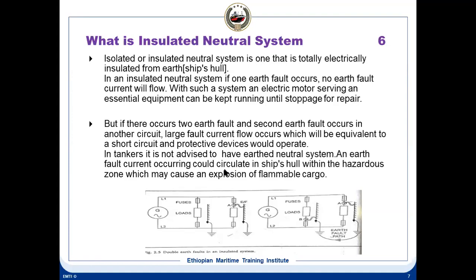So hope you understood what insulated neutral means. The purpose of the insulated neutral system is that in case of a single earth fault in one of the phases, your critical machinery should keep running, for example a steering gear motor. Suppose there is an earth leakage on one phase, it should still run. But if there is an earth leakage on two phases, it can cause a short circuit and the protective devices will trip the system. So it is basically only to protect in case of a single earth fault so that your critical machinery should run. This is known as the insulated neutral system.